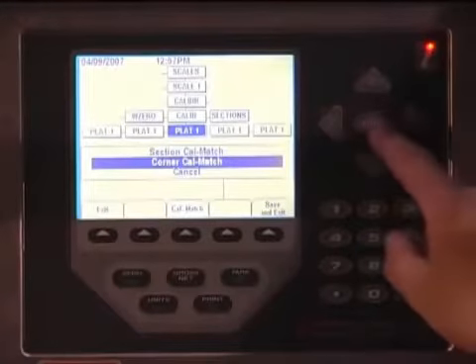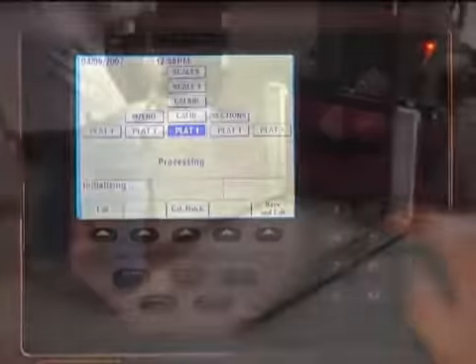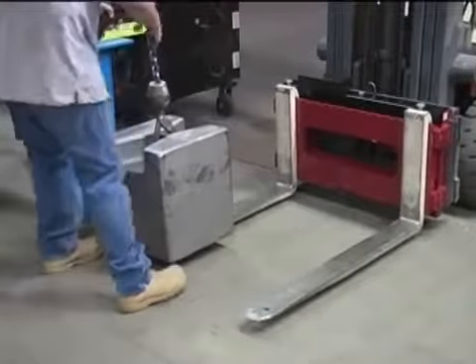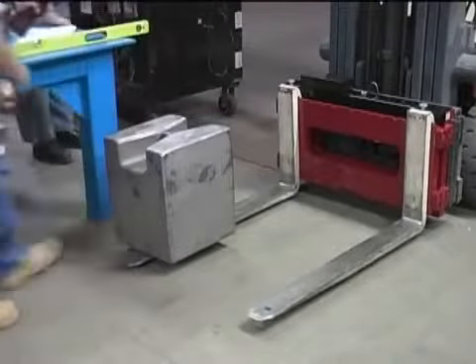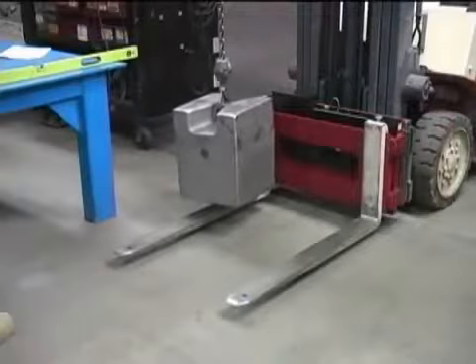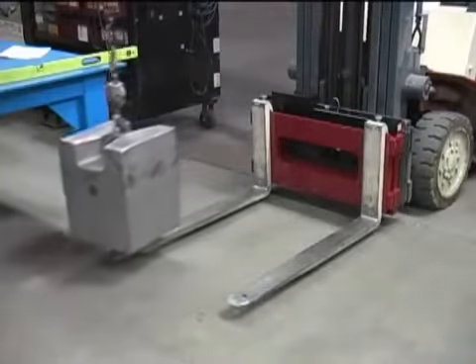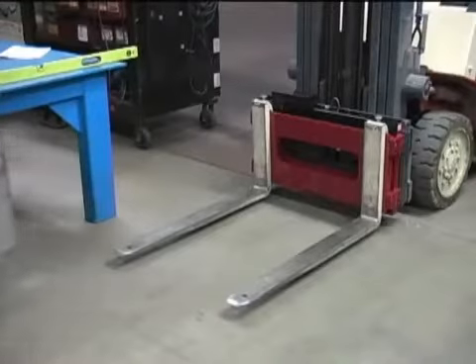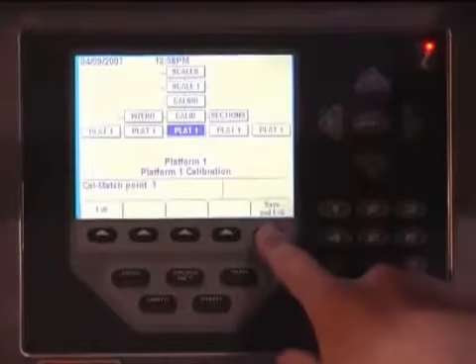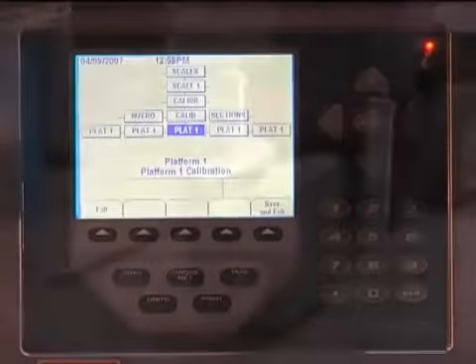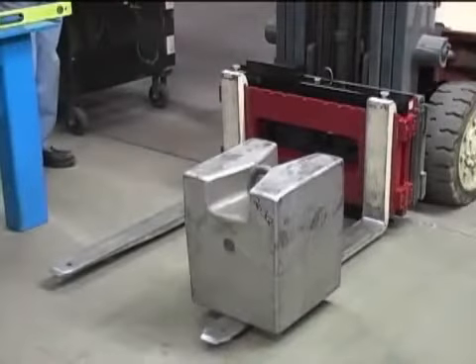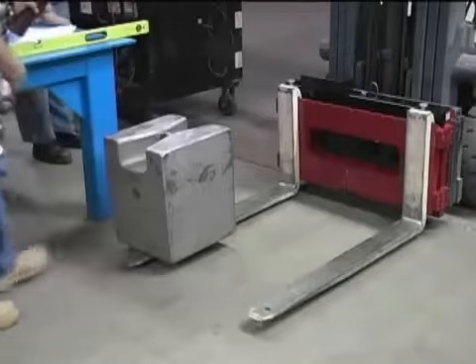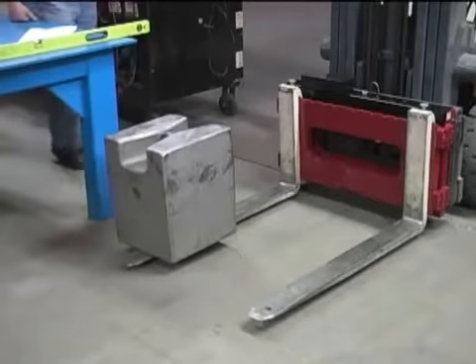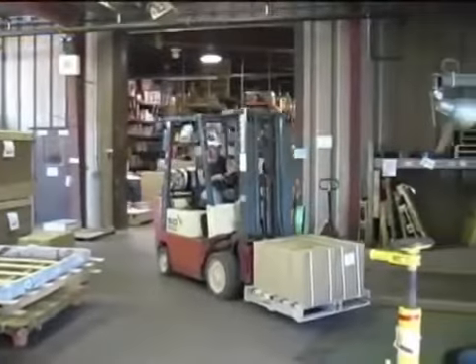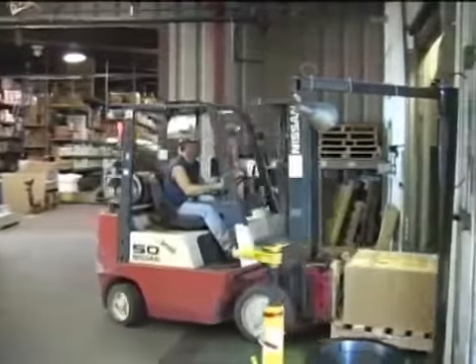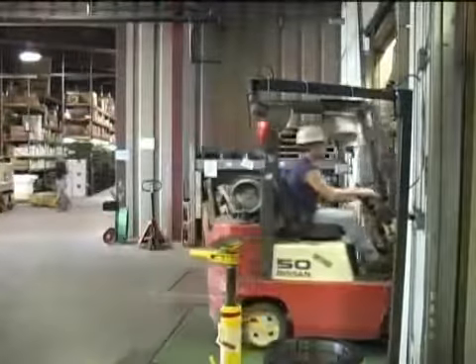The indicator will then prompt Cal Match point 2. Remove the weight from the left tine and place it on the right tine. You must use exactly the same test weight. When ready, press the Enter key. The calibration will finalize. When done, press the Save and Exit soft key. Calibration can be verified by placing the test weight on either tine. The readings must be the same. Once configuration of the user's parameters are all entered, the CLS should be ready for daily operation.